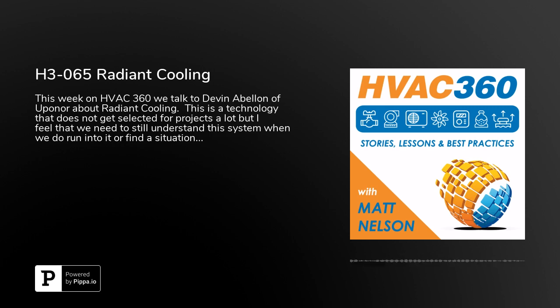If you look at how you're designing the entire system, you see right away that with a properly designed radiant cooling system that's operating properly, you're never going to come close to that dew point temperature. We've certainly seen issues in the past where radiant cooling systems have caused condensation. A lot of that had to do with older systems where we either didn't have the understanding of how to control for moisture or just didn't have the right controls in place.